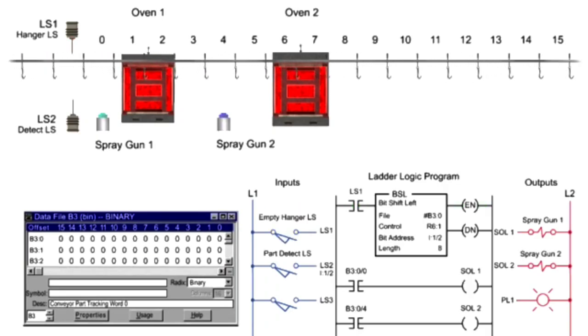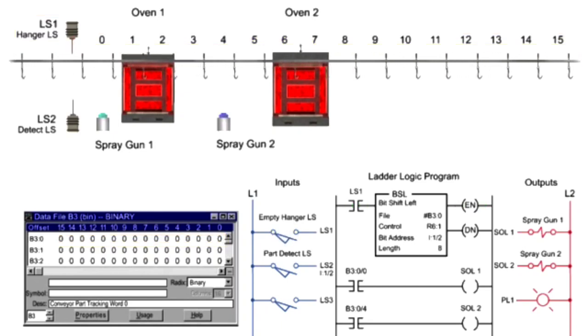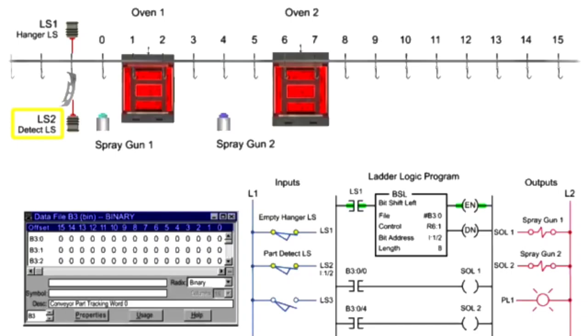As hooks are detected by LS1 limit switch, bits are shifted in file B3:0 from left to right. When parts are detected by the LS2 limit switch, logic 1 is loaded into the first bit of the shift register.